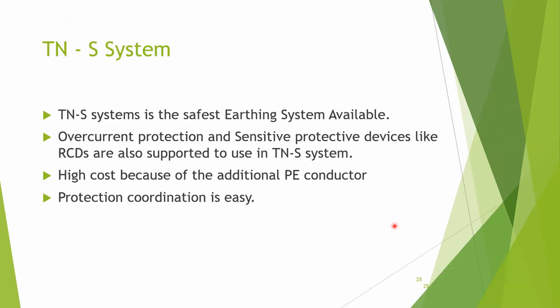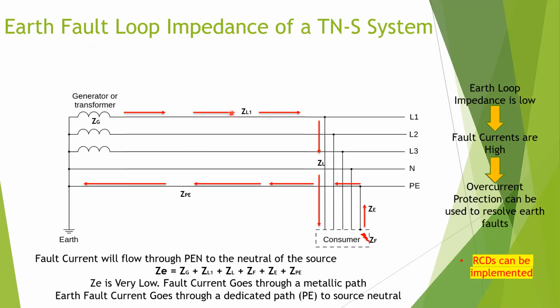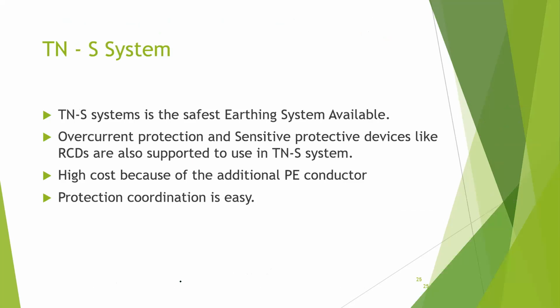And I have summarized the things: safest system and overcurrent protection, and here RCDs can also be implemented. I mentioned that, I think, because here the fault current flows through PE, not through the neutral. So we can implement an RCD between line 1 and neutral, and provide differential protection. Differential protection means we are measuring the difference between the currents in these two lines and tripping if there is a difference. High cost is also a drawback of this TNS system, and protection coordination is easy because it is easy to find faults.